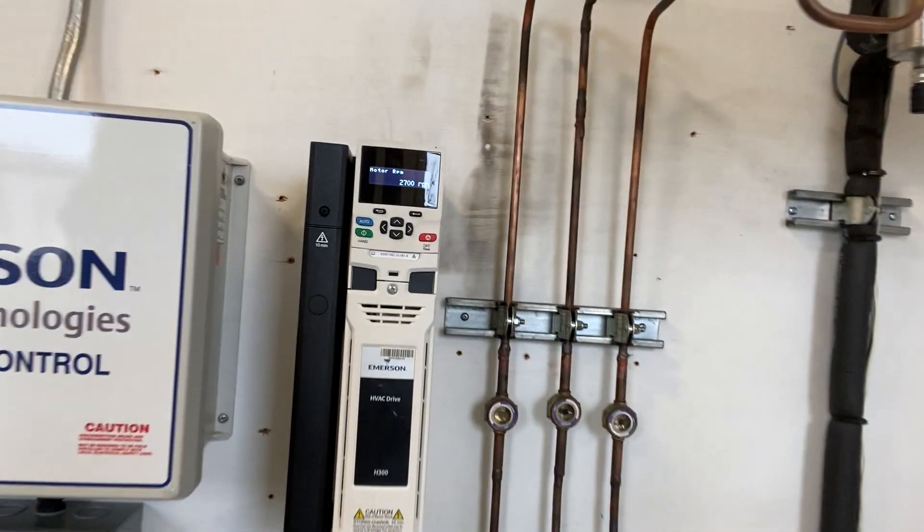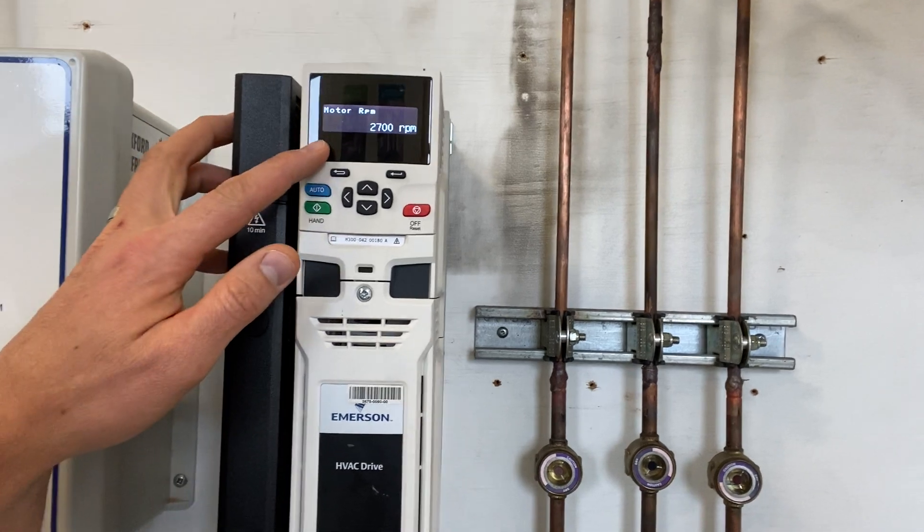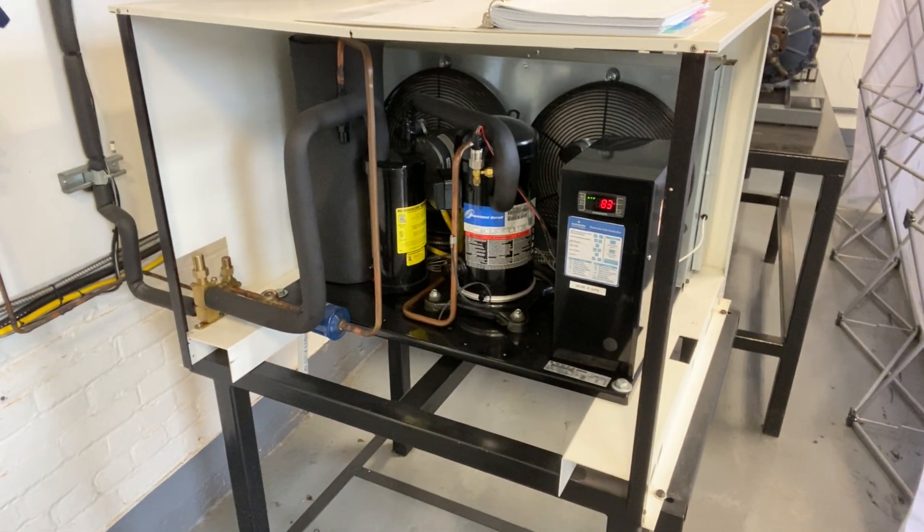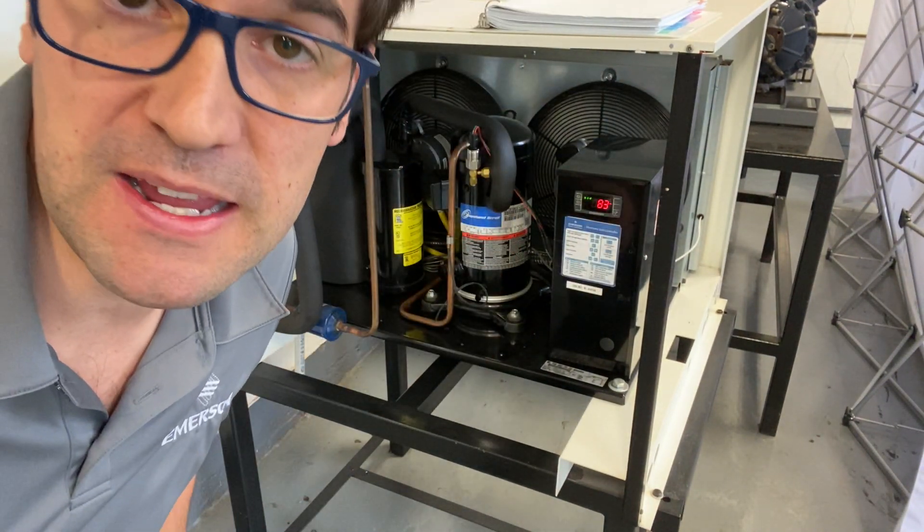Well, you can. You can put a drive on a fixed compressor. If the compressor is oversized, you potentially can add a drive onto that discus compressor or that scroll compressor. There are limitations — you need to check out Application Engineering Bulletin 1369, I will put that in the description. Right here I've got a fixed compressor with a drive running at 2700 RPMs, just a scroll compressor, a ZB-15. So you can do it, but just make sure you check those limitations.